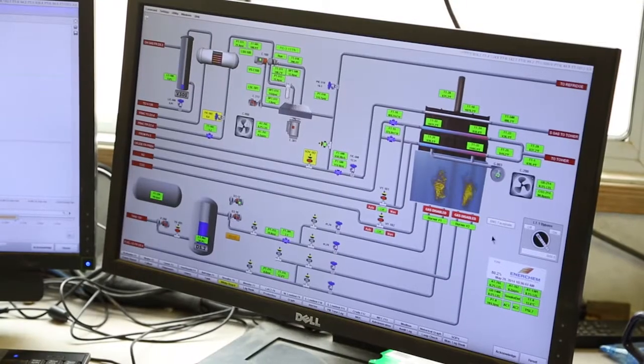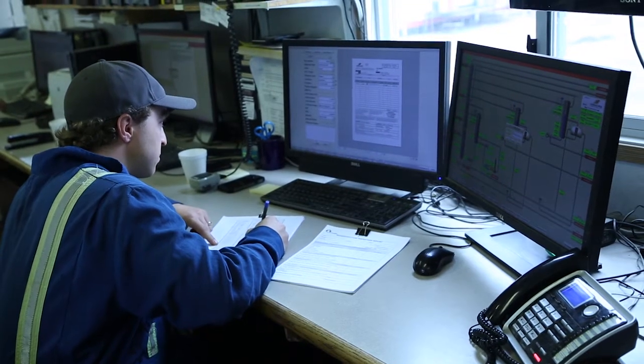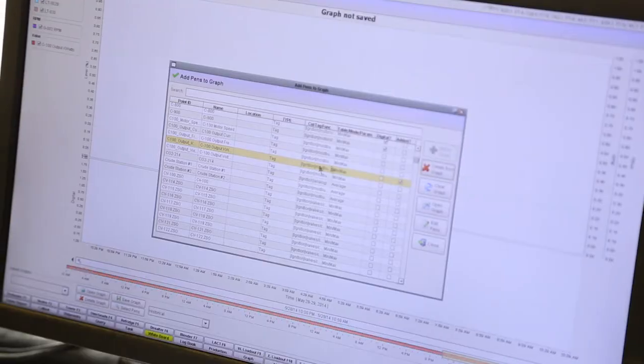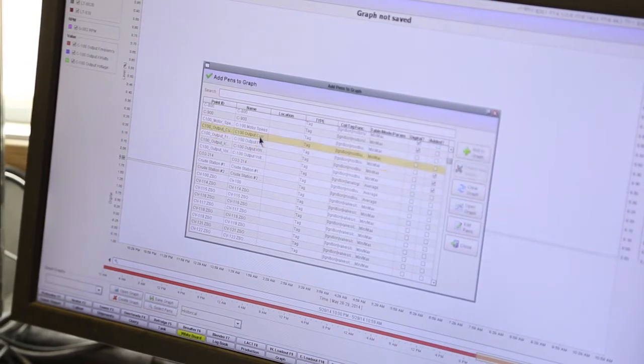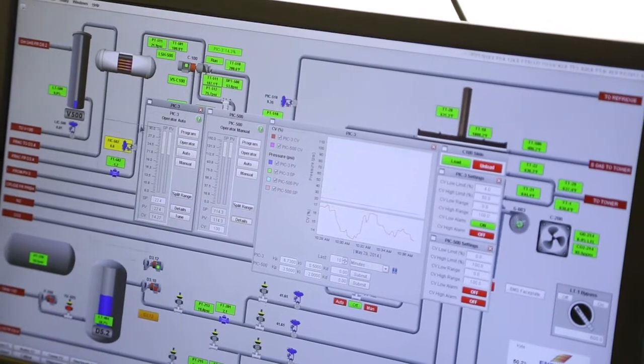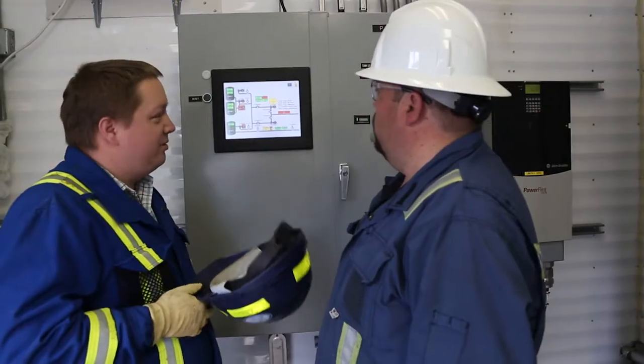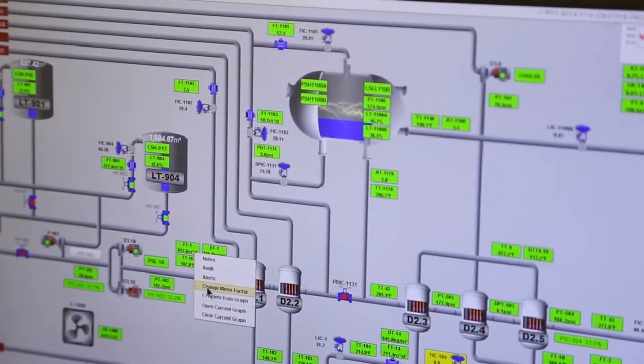Enterchem has a few different control networks, including EtherNet/IP and Modbus. Ignition provides a flexible solution for communicating with these different end devices based on OPC UA. Ignition is also acting as an OPC UA client to other PLCs that have an embedded OPC UA server, and all of Enterchem's facilities are interconnected to each other through OPC UA, sharing live plant information between them.